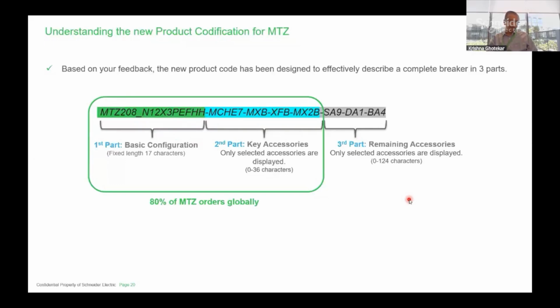Coming back to the part number now, MTZ Active is with the product selector. So I will go through this. Now, once you select, let's say in the product selector, it will by default have a meaningful part number. Meaningful means it will indicate like MTZ1, that is size 1, MTZ2, MTZ3, 08, or the type rating of a breaker, the fault capacities, it's H1, H2, or depending on the applications. The type of trip unit is 2X for MTZ MicroLogic X, or 2A or 2E for MTZ Active, 3-pole, and so on. So this will be the standard one.